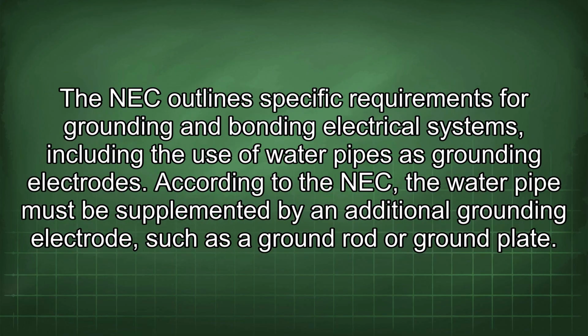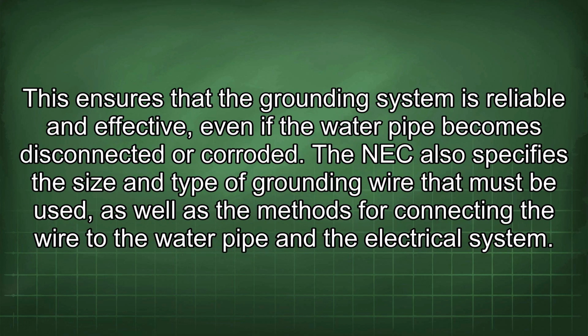The NEC outlines specific requirements for grounding and bonding electrical systems, including the use of water pipes as grounding electrodes. According to the NEC, the water pipe must be supplemented by an additional grounding electrode, such as a ground rod or ground plate. This ensures that the grounding system is reliable and effective, even if the water pipe becomes disconnected or corroded. The NEC also specifies the size and type of grounding wire that must be used, as well as the methods for connecting the wire to the water pipe and the electrical system.